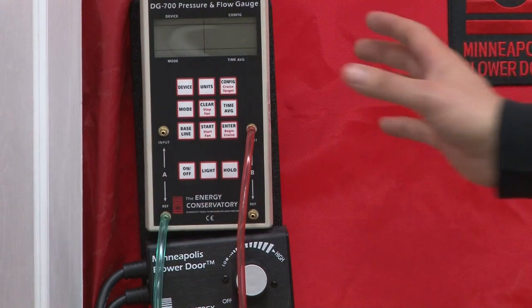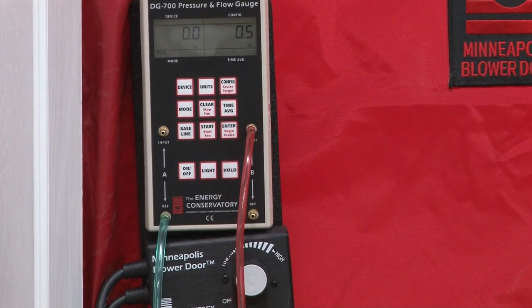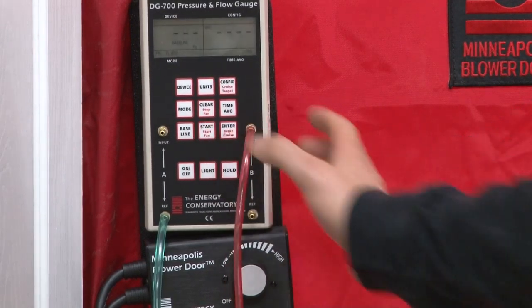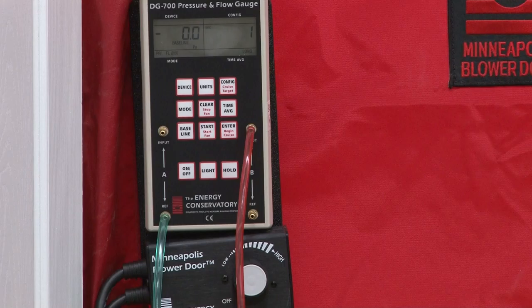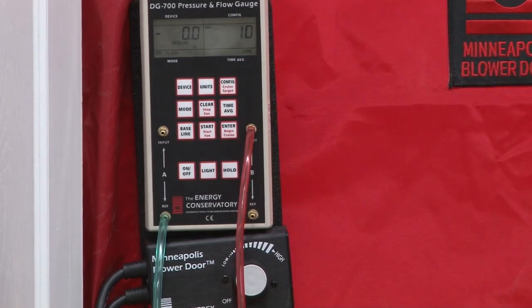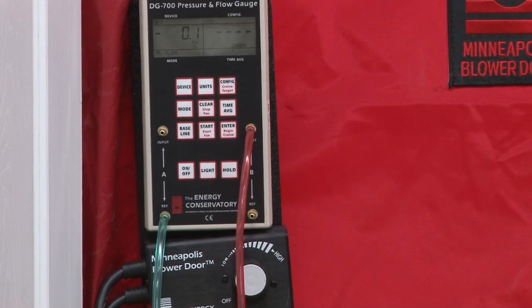We've got five button pushes once we get our manometer turned on. On is the first button push, then we're going to push mode, then mode again, then baseline, then we're going to push start. That's going to start our process of gathering information to determine our baseline — the difference from outside to inside. You'll see the countdown start; once it hits 10 seconds it'll click, alerting you to push enter and store the information into the DG-700 manometer.